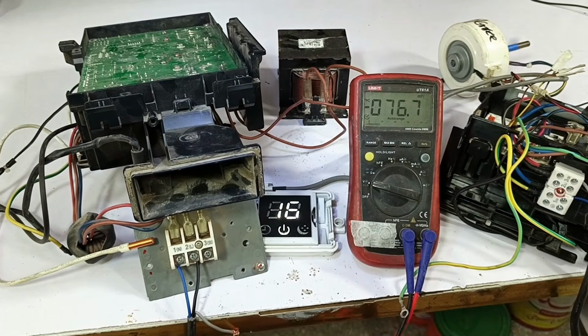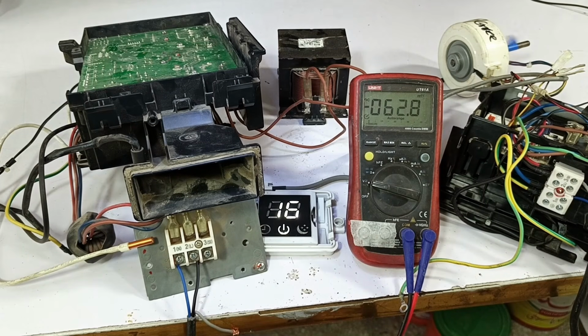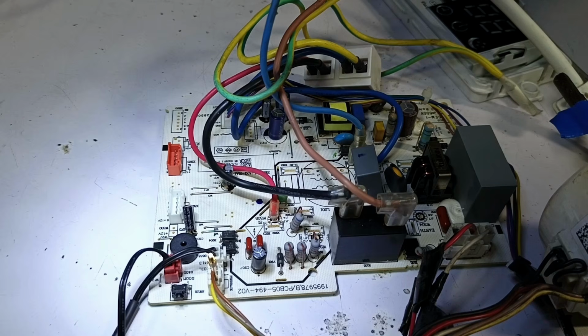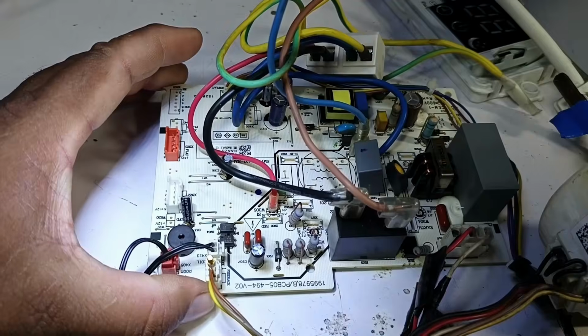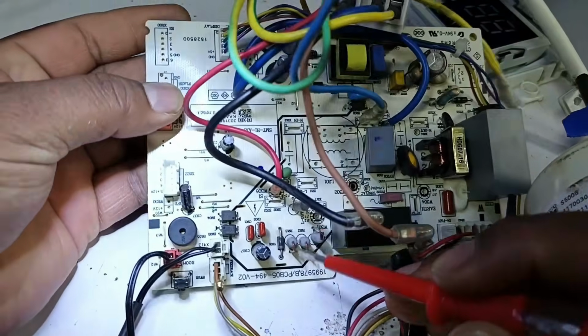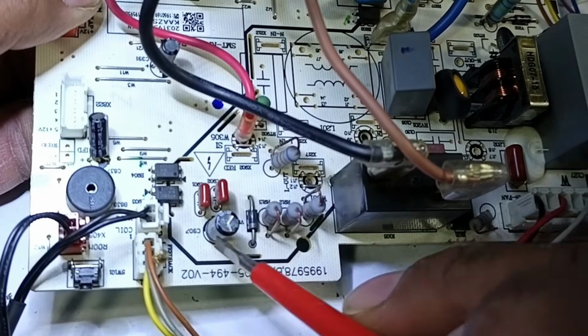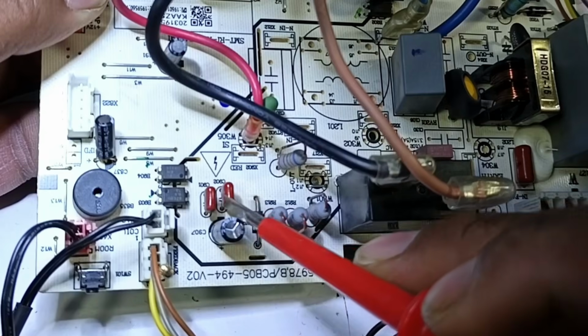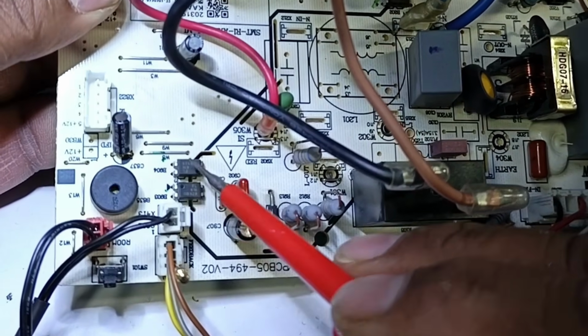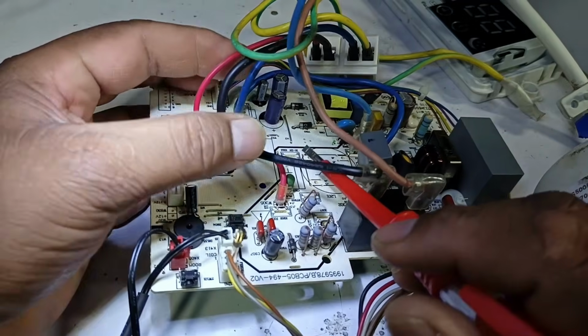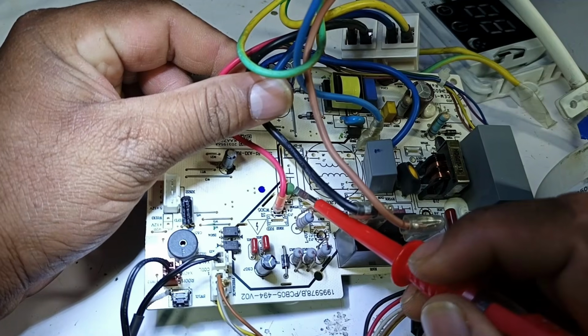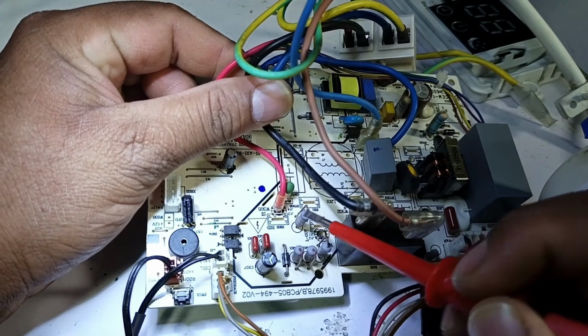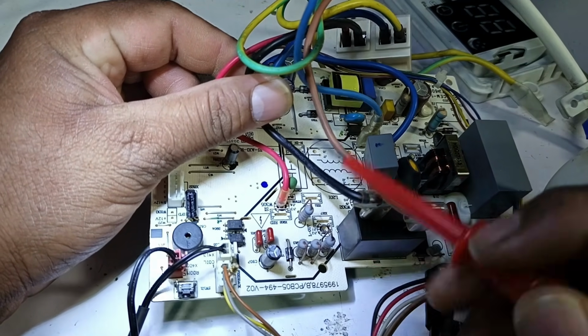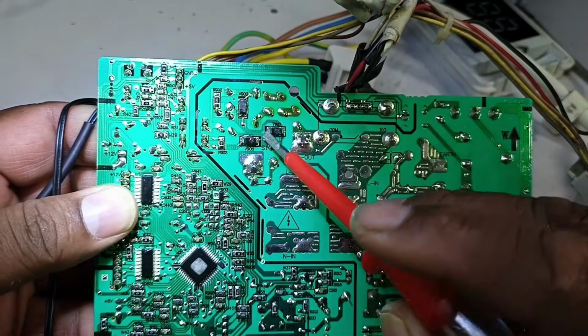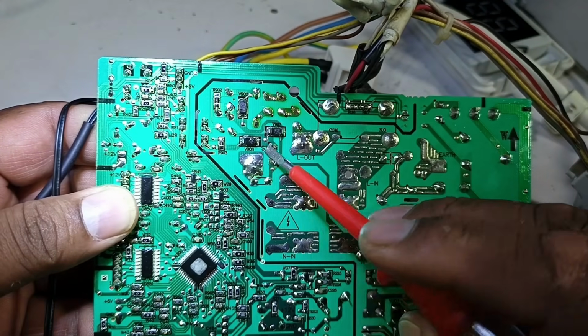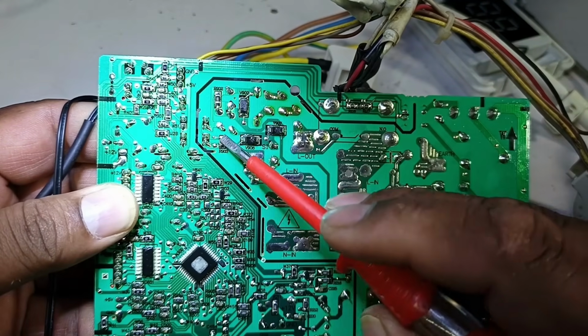So now we will see whether the fault is in the indoor or in the outdoor. This also needs to be checked. First of all, we will test the indoor and the circuit installed here. You can see all of these are resistances, diodes, capacitors, ceramic capacitors, and here are these 2 optocouplers. Apart from this, you can see there is a PTC sensor installed here, and here as well, there is a resistance, which is also part of this circuit. Along with this, all these diodes and resistances installed here together are both receiving and sending the communication.